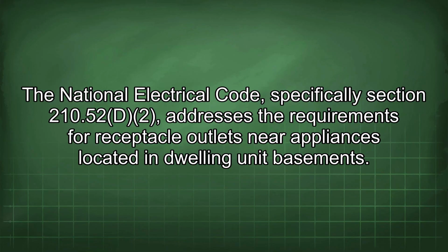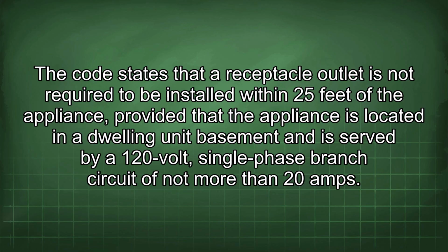National Electrical Code, specifically Section 210.52(D)(2), addresses the requirements for receptacle outlets near appliances located in dwelling unit basements. The code states that a receptacle outlet is not required to be installed within 25 feet of the appliance, provided that the appliance is located in a dwelling unit basement and is served by a 120-volt single-phase branch circuit of not more than 20 amps.